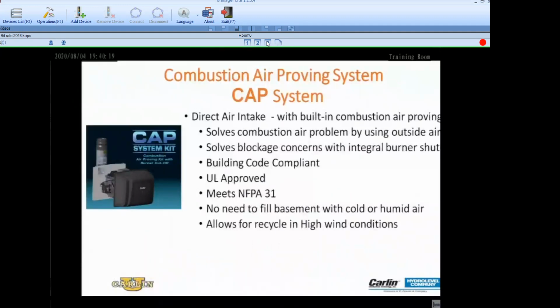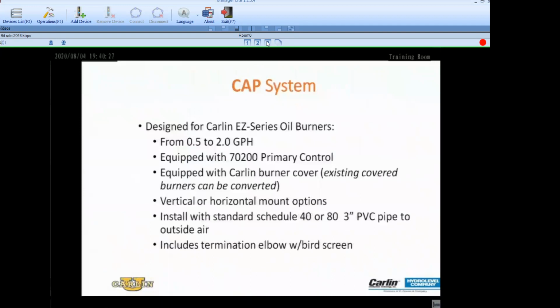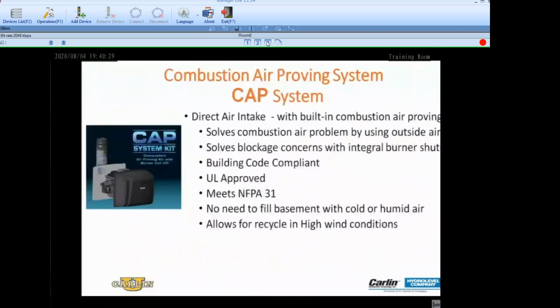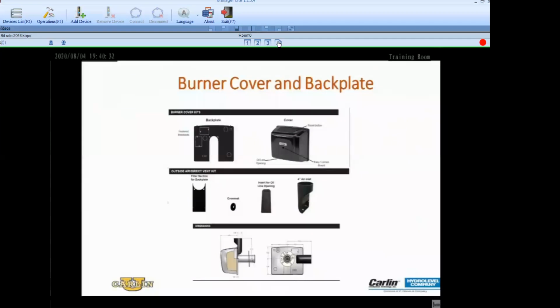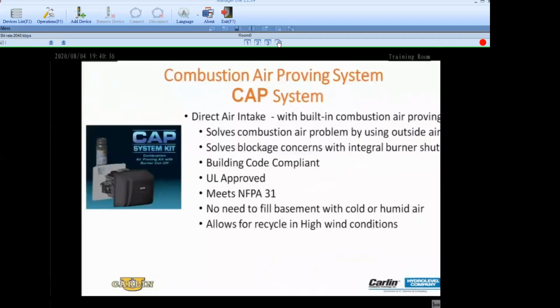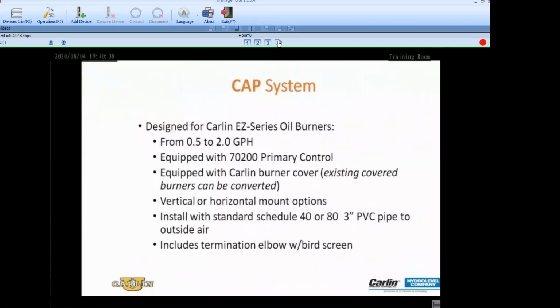Burner covers: a burner cover with a proper adapter that you can connect to PVC pipe or galvanized pipe, and bring combustion air directly to the appliance. Here's my pitch, the Carlin CAP system, the combustion air proving system, which essentially is using the cover system that you see here. The CAP system is UL and NFPA approved, designed to work with a Carlin EZ Series burner. And it's interlocked, and that's the UL and NFPA requirement, that you interlock the combustion air when it is introduced by mechanical means.